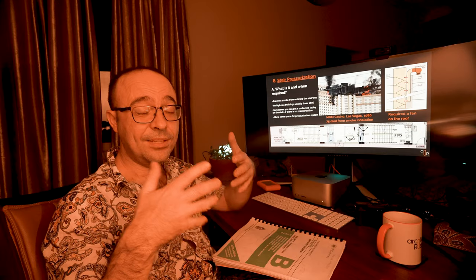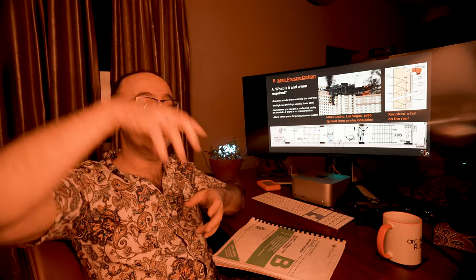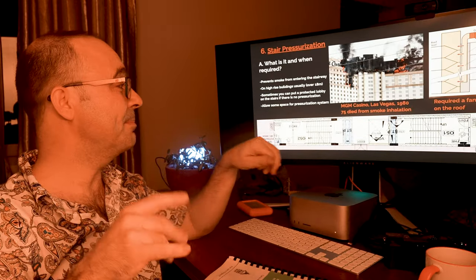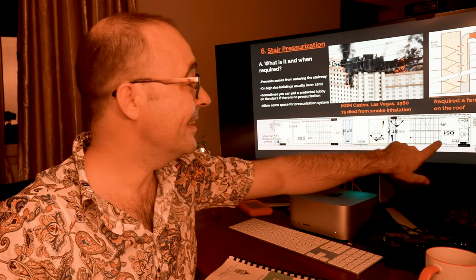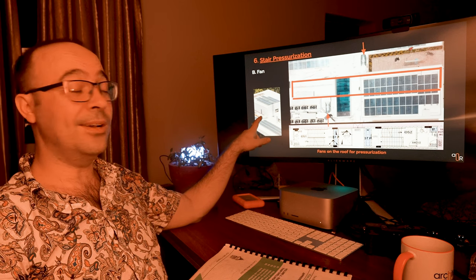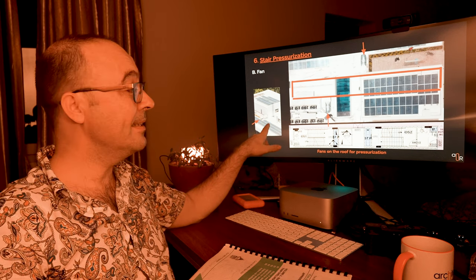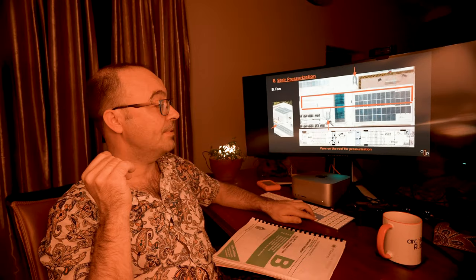Stair pressurization stops smoke from entering the stair. If smoke does get in, the pressure should ventilate it out. There's usually a fan at the top that pulls the smoke out. Usually on buildings over 18 meters, if you don't have pressurization, sometimes you put a lobby on the stairs instead. You've got to make sure you add some space next to the stair, usually on the landing side, for pressurization — that allows air to go up and there's a fan at the top. There'll be some space on the roof you need to allocate for that fan.